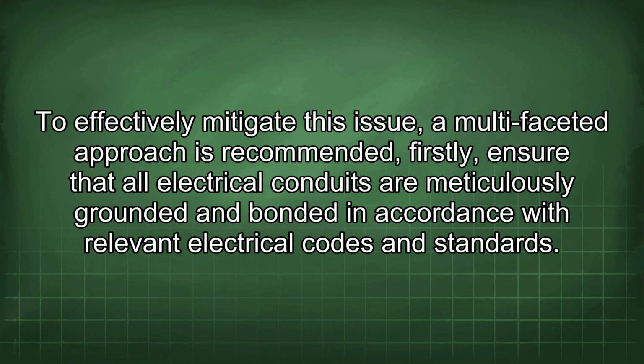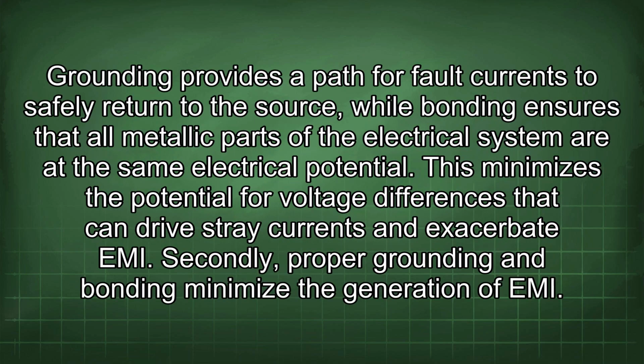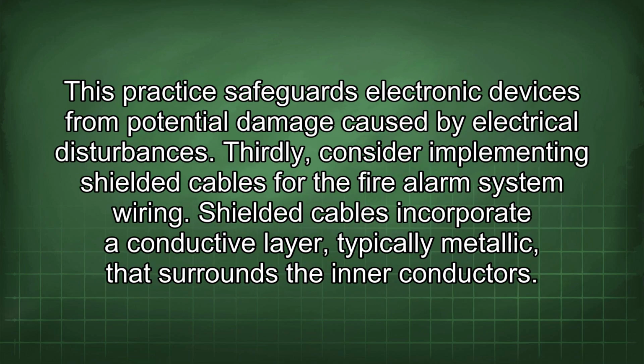Firstly, ensure that all electrical conduits are meticulously grounded and bonded in accordance with relevant electrical codes and standards. Grounding provides a path for fault currents to safely return to the source, while bonding ensures that all metallic parts of the electrical system are at the same electrical potential. This minimizes the potential for voltage differences that can drive stray currents and exacerbate EMI. Secondly, proper grounding and bonding minimize the generation of EMI. This practice safeguards electronic devices from potential damage caused by electrical disturbances.